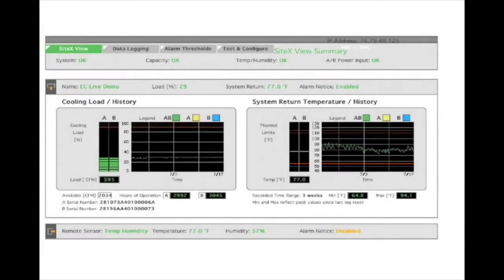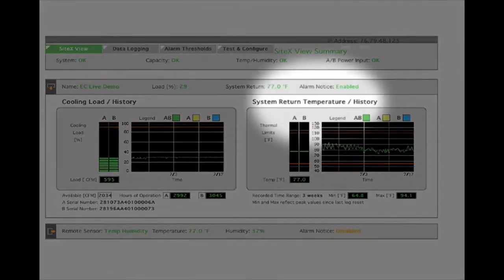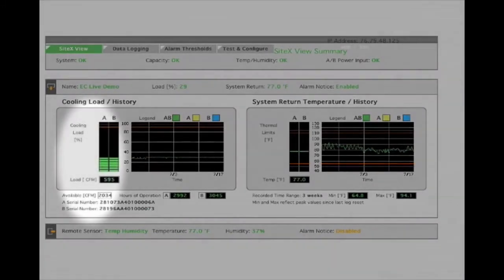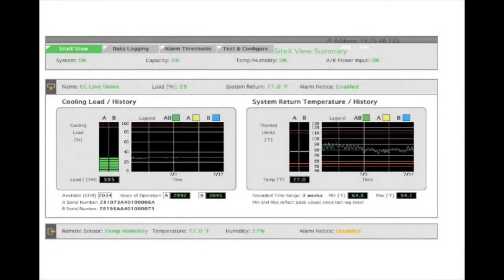The on-screen user interface allows users to track real-time information and log data, including cooling load, system return temperatures, humidity, and alarms to make informed operational decisions. Users also have the ability to know the CFM in every rack and can aggregate this information to determine how much air is required from the CRAC units, drawing only the amount of air needed to cool the equipment while eliminating over-provisioning. The resulting reduction in fan speed reduces energy and therefore contributes to additional savings.